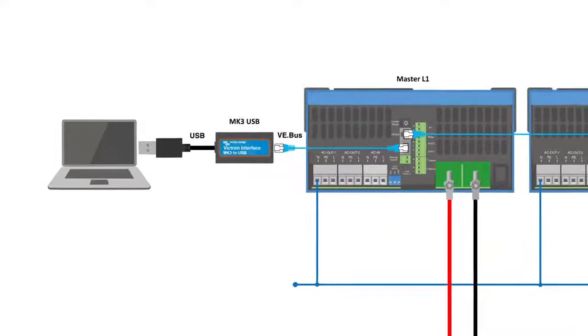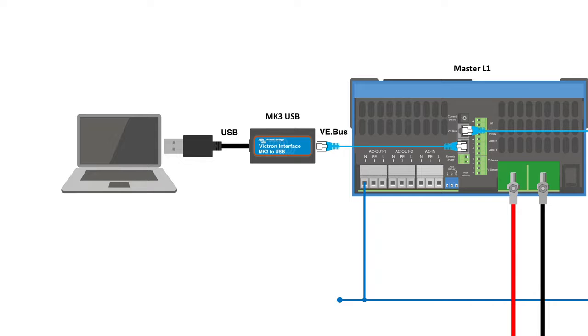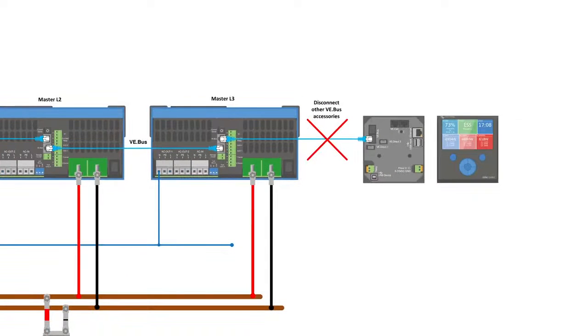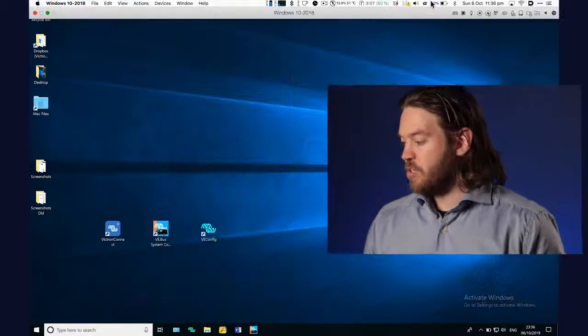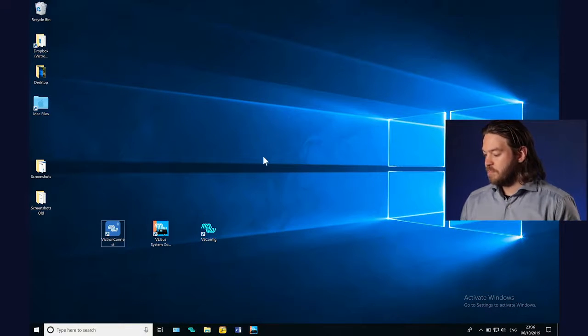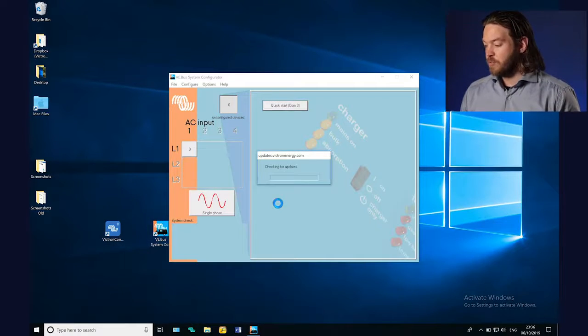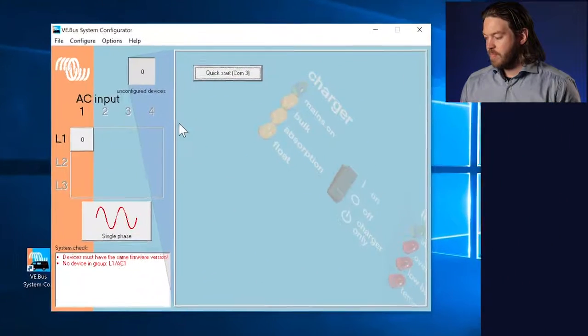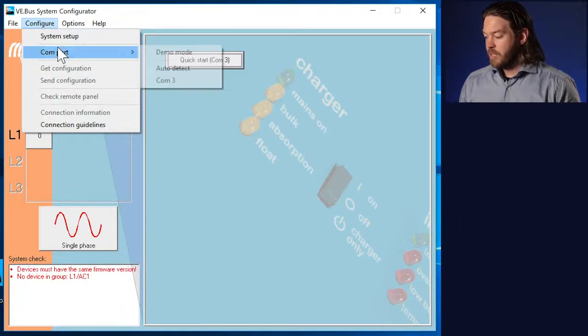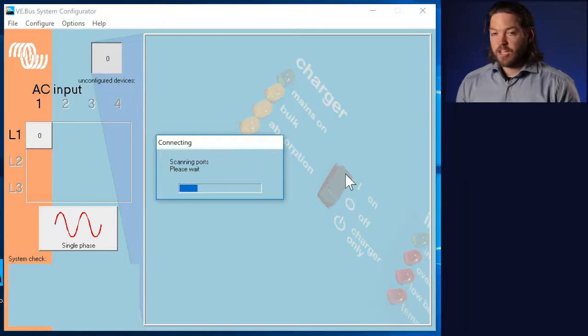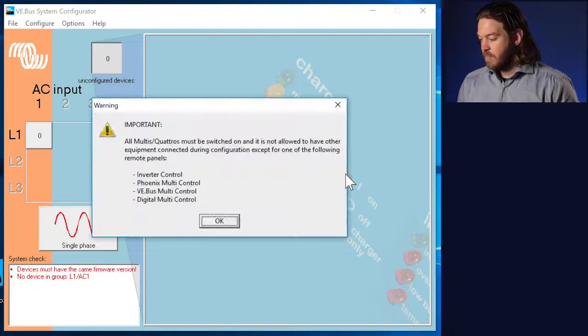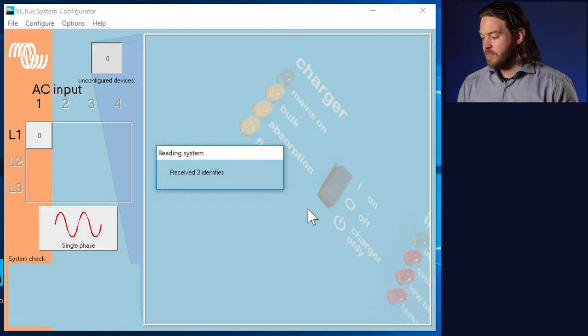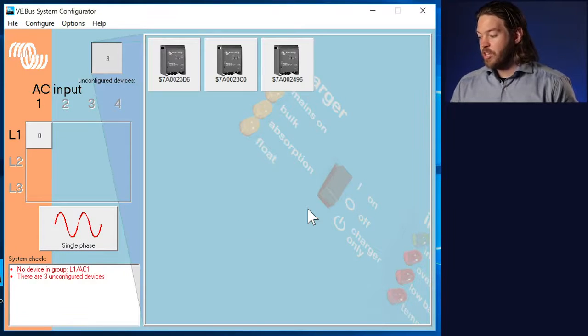I've connected the Multi+2s with the MK3 to USB adapter and disconnected the Color Control and any other accessories. I'll make sure that the MK3 is connected. It is. I'll open up the VE.Bus System Configurator tool. I'll then go up to the Configure menu, select the COM port and Auto Detect. It'll scan the ports and look for the devices. It'll remind us again to disconnect any accessories we might have connected, Color Controls, Digital Multi Controls, etc. We have those disconnected, and we can now see the 3 units as unconfigured devices in the software.